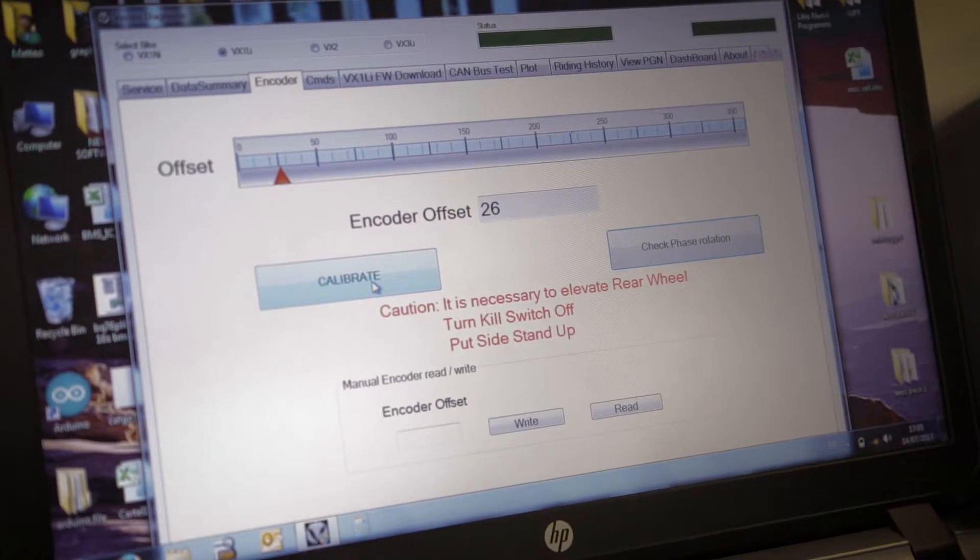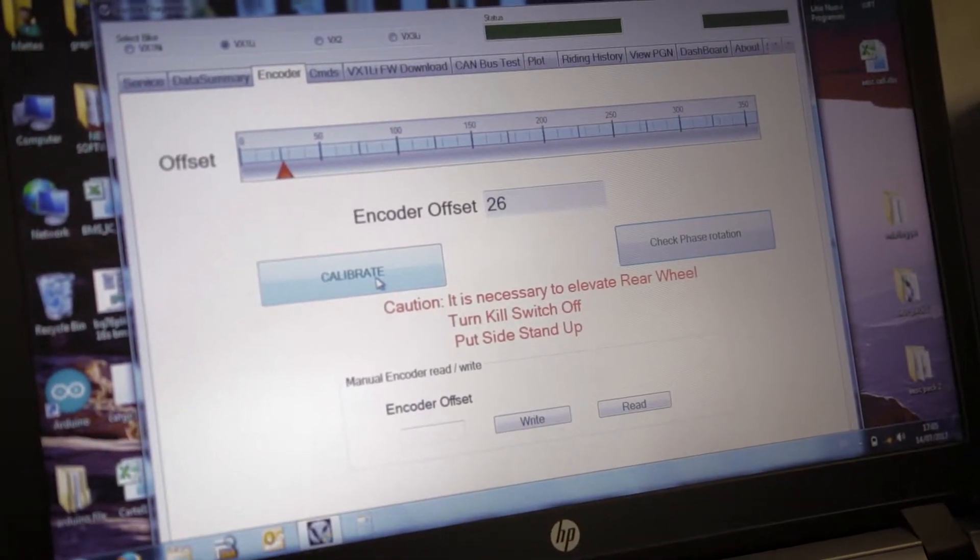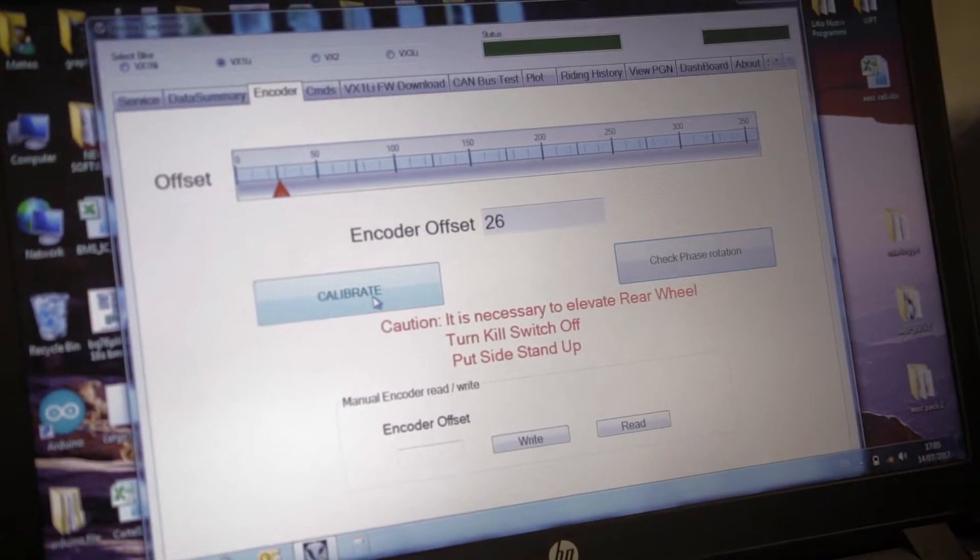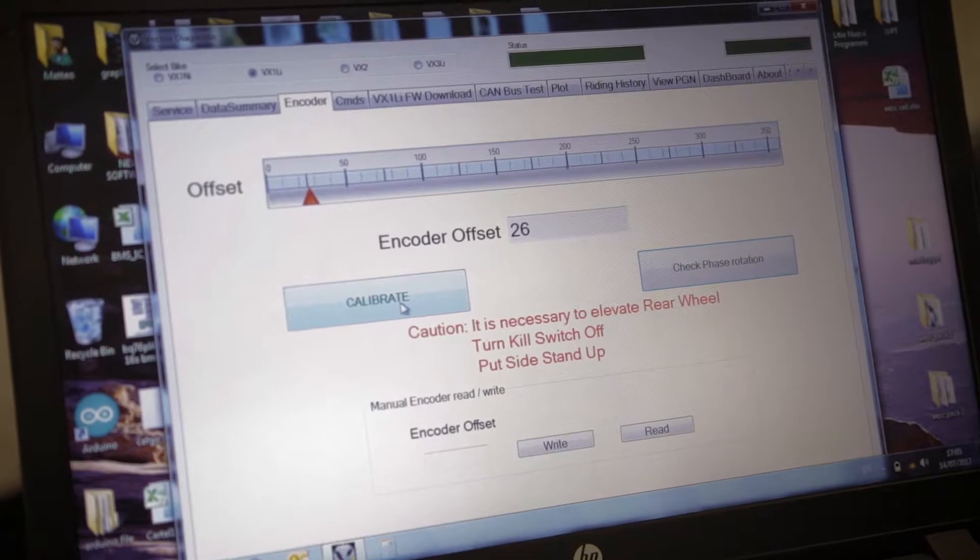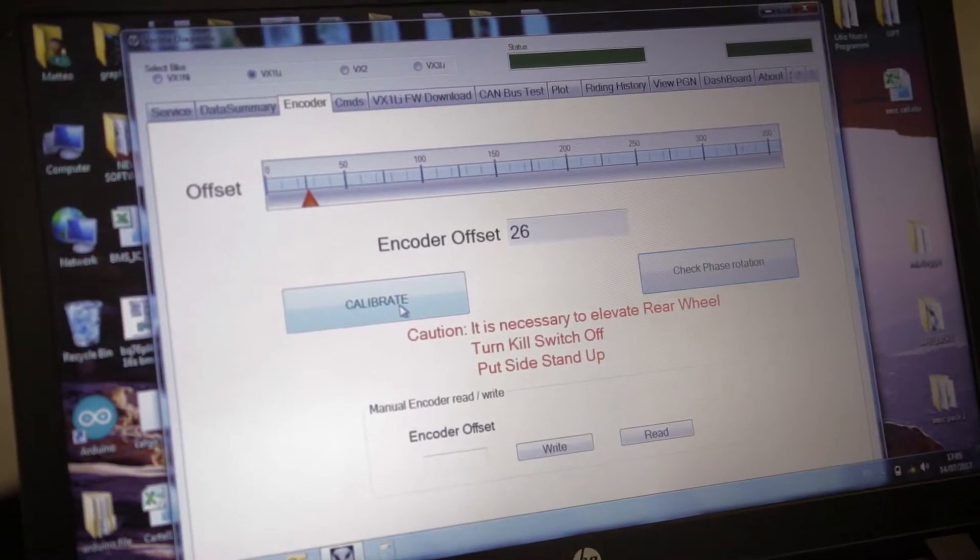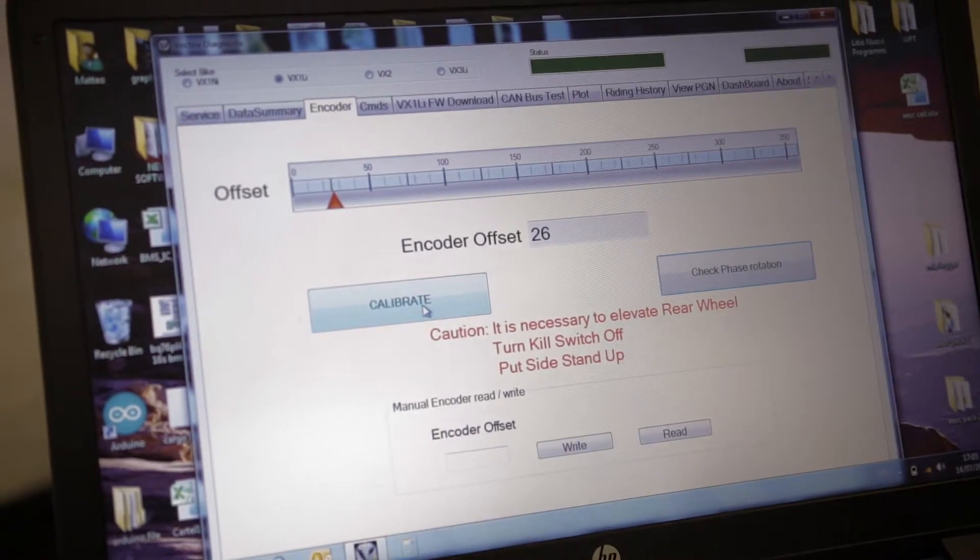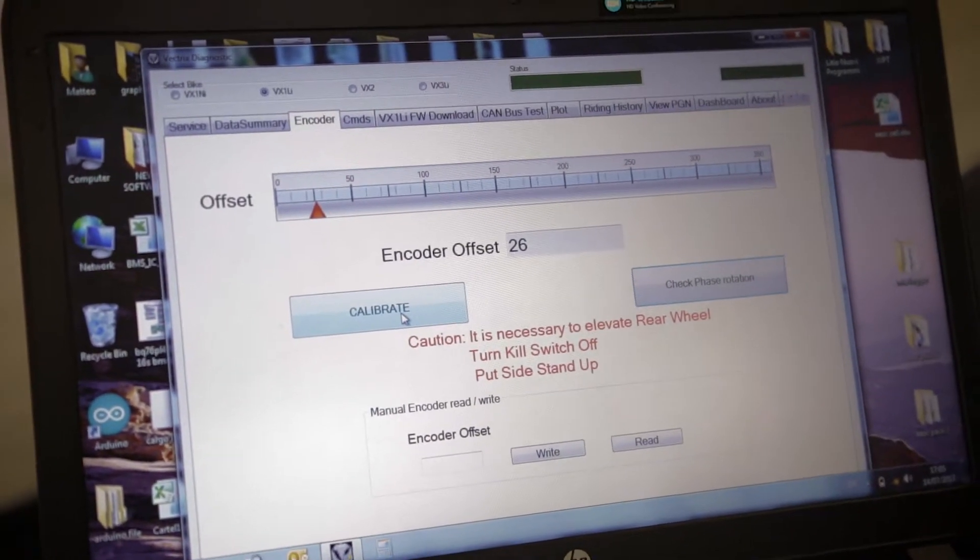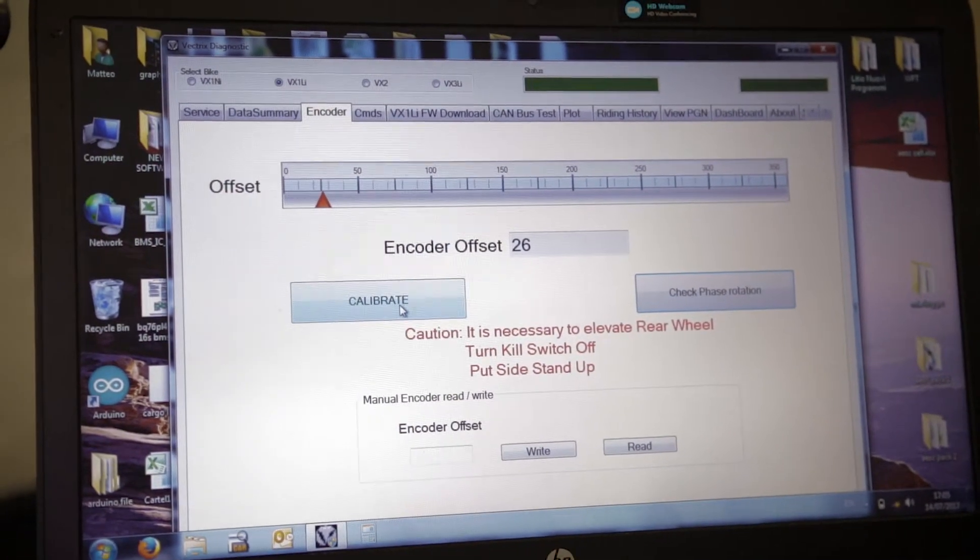Calibration of the encoder is simply a procedure that lets the motor controller recognize the position of the motor in reference to the encoder. Once they are calibrated, they're in phase and the motor has optimal efficiency. If for any reason this angle is wrong, the motor will behave badly or when you accelerate it will not be smooth.